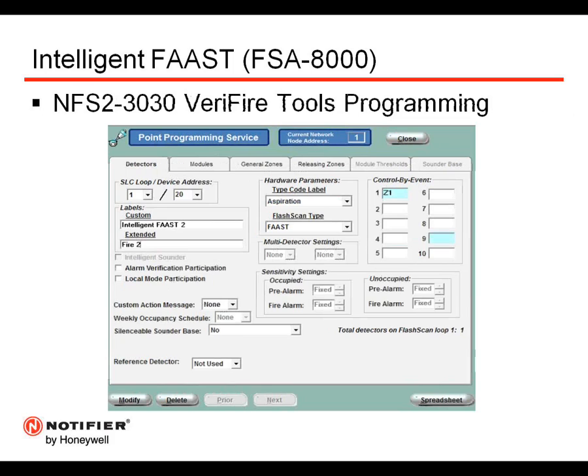And here's a similar screenshot from the NFS2-3030 for VeriFire Tools programming. Very similar, you still have the same programming. The NFS2-3030 supports up to 10 CBEs, or control by event programming options. Again, the sensitivity levels are grayed out. And with the NFS2-3030, we do support that reference detector, which would be programmed down here to associate the reference detector.